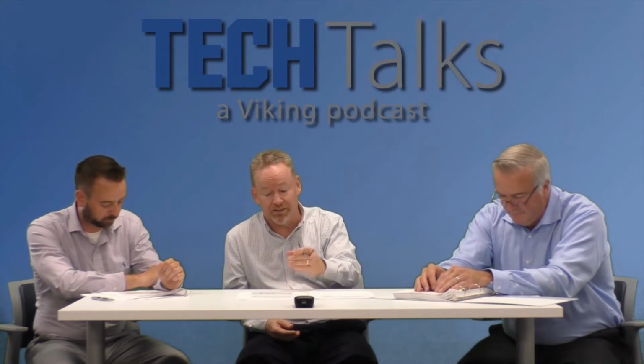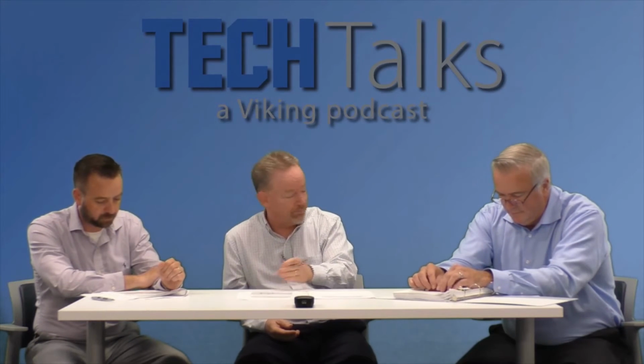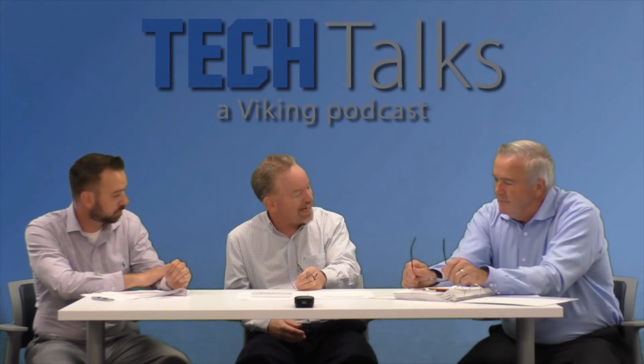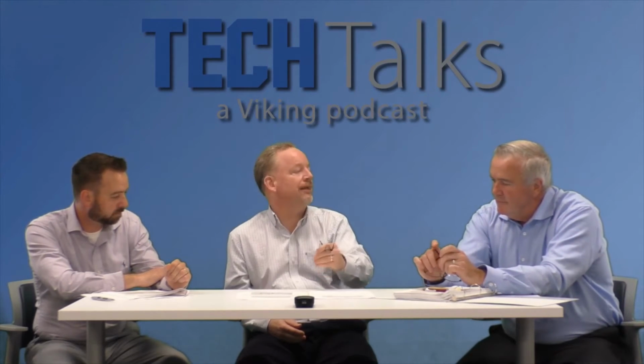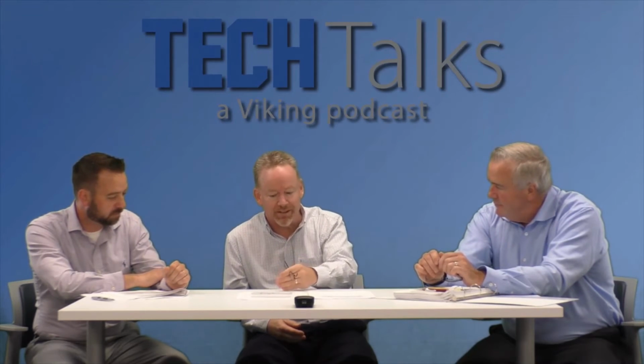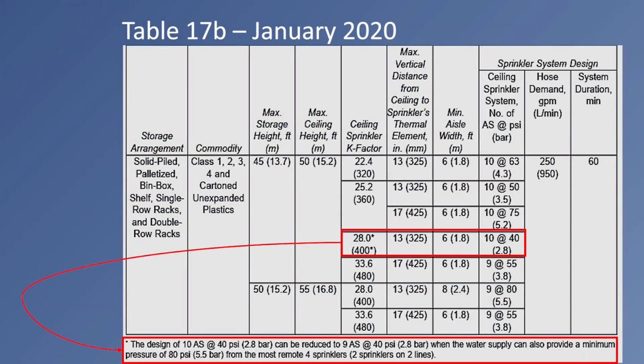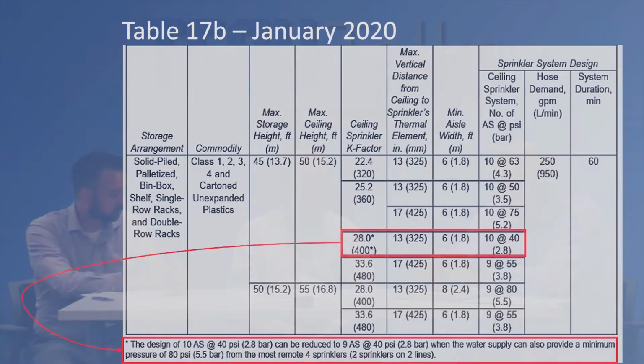It wound up with a significant change in January of 2020 that really, 17B doesn't look anything almost like it did before, because the K-28 is sitting there, the K-33.6 obviously is there as well, but the K-28 has a kind of a dual life to it. It's got a 10 sprinkler design and also a 9 sprinkler design, because in the table itself, it has a 10 sprinkler design like everything else, but there's that lovely asterisk and note right there that says you can go to 9. That was all based on the testing and work that we had done at FM.